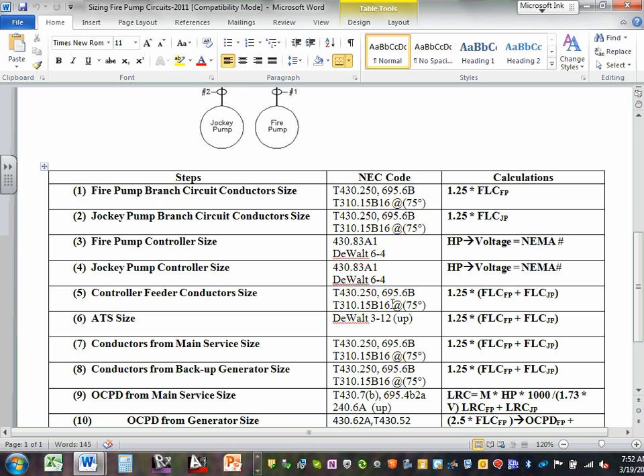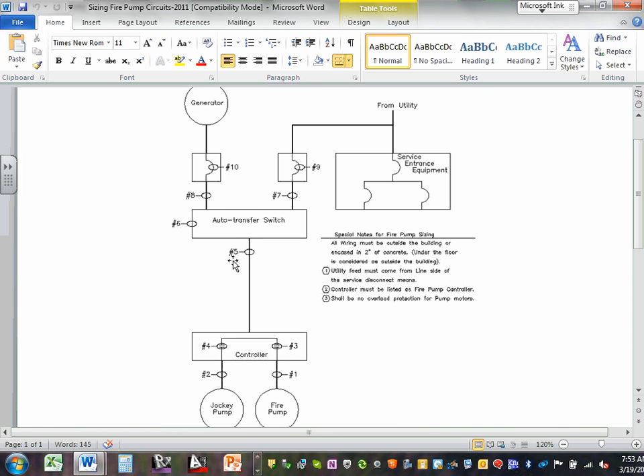Where do you find the references about it? I gave you the NEC code book references: 430.250, 695.6(B). Cables will be from 310.15(B)(16) at the 75-degree column. So when you size the feeder for the 2 of them, here's what you need to do. The controller feeder, you take 1.25 times both full load currents. Did you see that? You multiply by both full load currents, you add them up, and you size your conductor. Any comments? Any questions about number 5? Questions about number 5? Number 6.